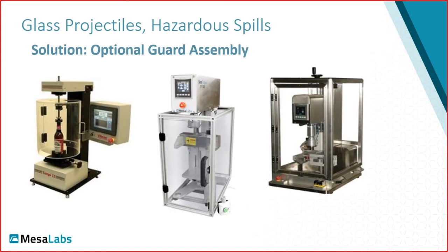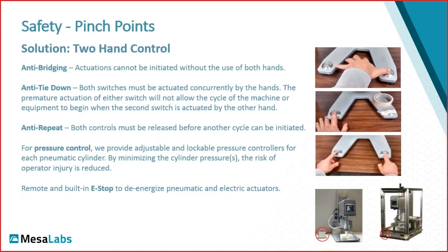Another safety consideration that comes with both manual and automated testing is the spill of hazardous materials, blood products, or corrosive materials, and the breakage of glass bottles and pressurized bottles creating projectiles. The solution to that on our machine is to guard the system. So if there's any issue, it stays within the enclosed area and it doesn't affect the operator.